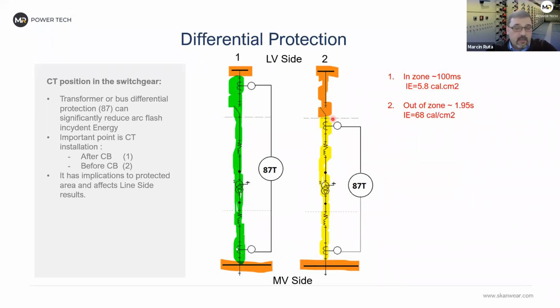And for the differential, it depends how the system is grounded. Is it an insulated system or high resistance? It may not pick up in-zone faults even. Depends on configuration, of course.